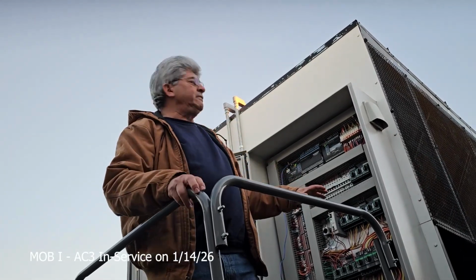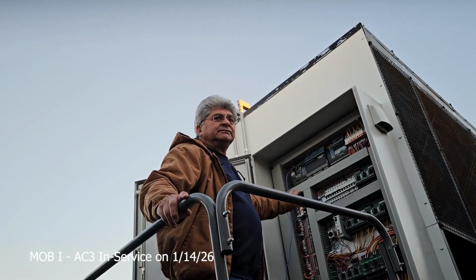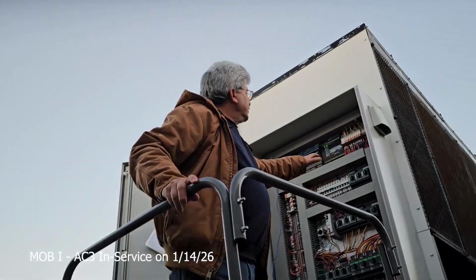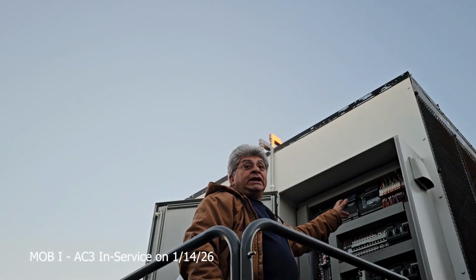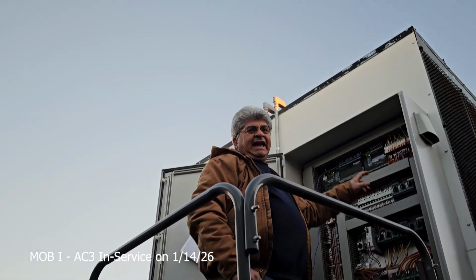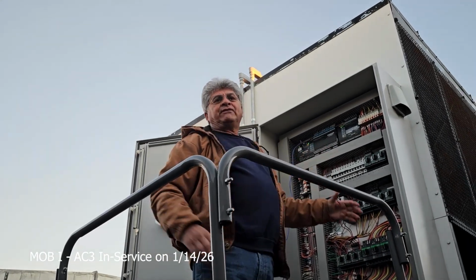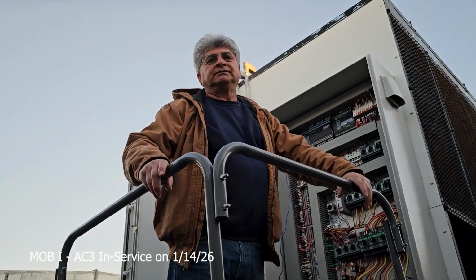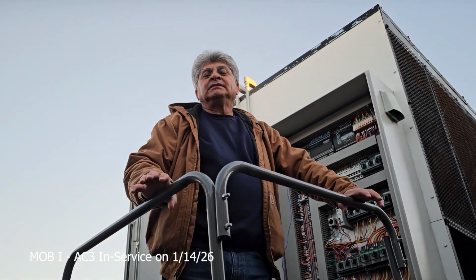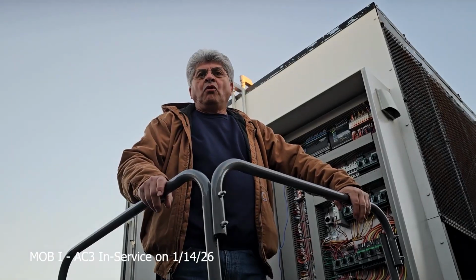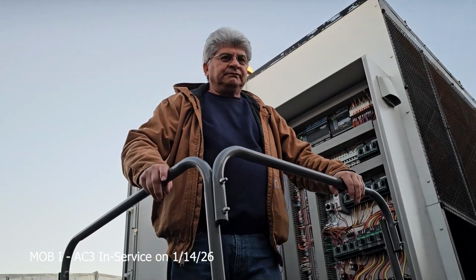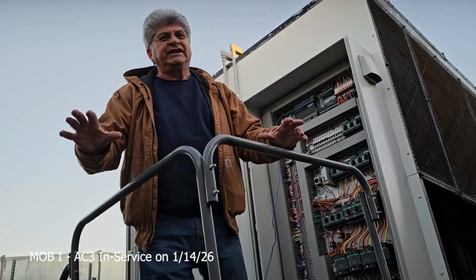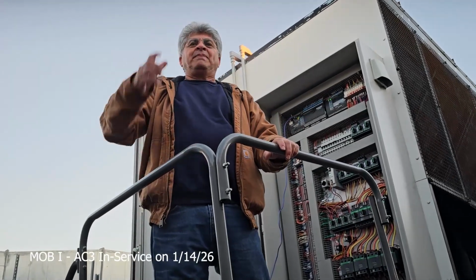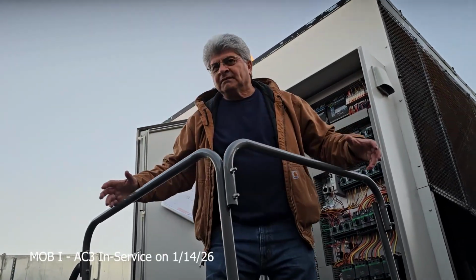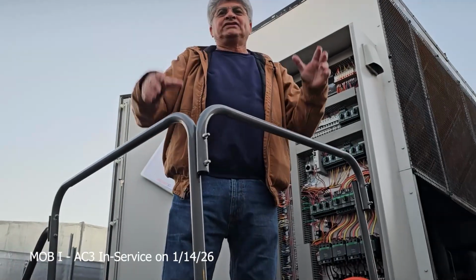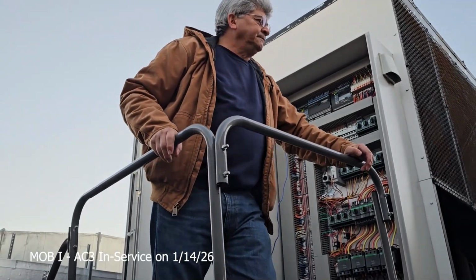That master resets all your controllers inside, and then they all... So this has a time delay. When it sees power go off, it has a time delay as well. So there's several time delays. That's why it takes so long. So don't panic if you don't see the whole machine. It's not like a package unit. You turn on your package unit, 20 ton, both circuits kick on, everything runs. So it's not like that.